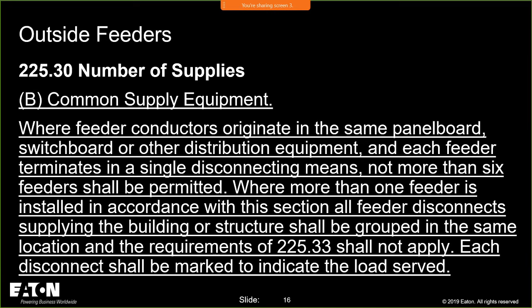So where feeder conductors originate, here's the language that they accepted. Where they originate in the same panel board, switchboard, or other distribution equipment, and each feeder terminates in a single disconnecting means, not more than 6 feeders can be permitted. So now we're on that same 6 disconnect rule topic. That's why I put it in here. I'm allowed to have up to 6 feeders. But remember, they all have to start at the same piece of equipment, and they have to end on an overcurrent device. And each disconnecting means has to have a label on what they serve.